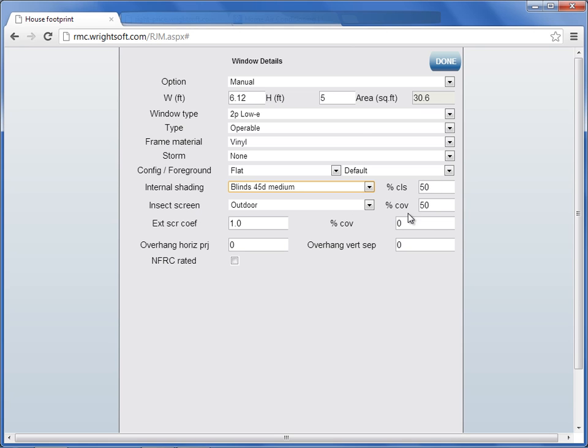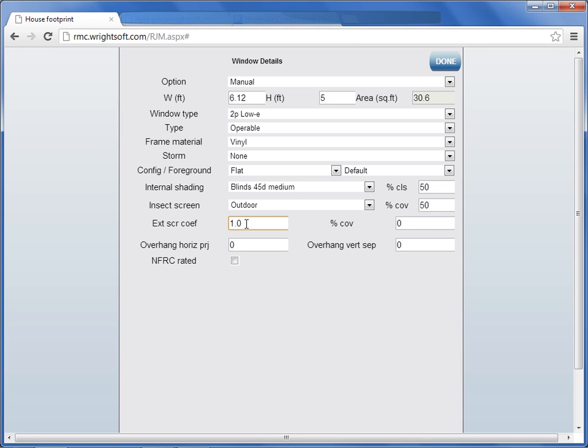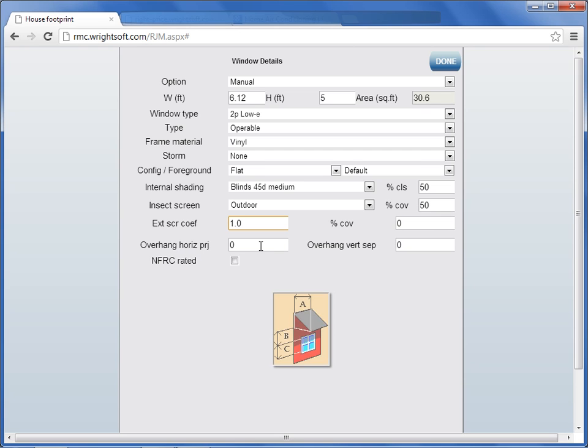Next, you have insect screen in percent coverage. The next row stands for external sunscreen shading coefficient. The most common type application here is a window covering that's applied on the exterior of a window, and that reduces the amount of sunlight that passes through the window. Over to the right is the percentage coverage. The next row is overhang horizontal projection. If you've got a porch or an awning that stretches over the window, this is your horizontal projection.